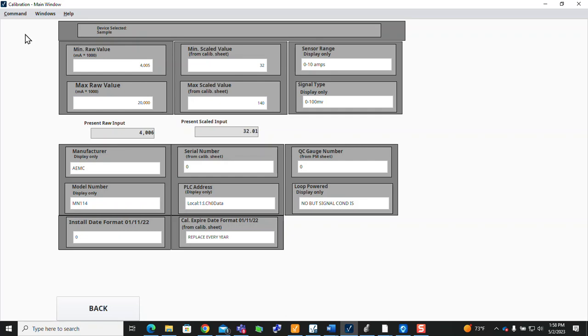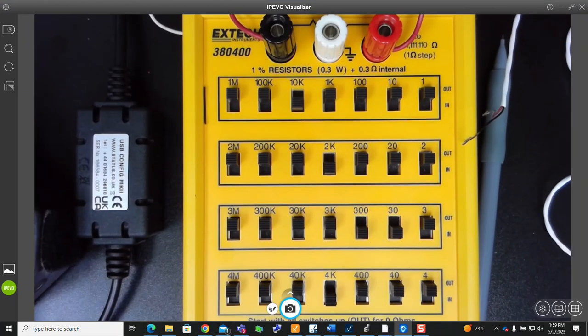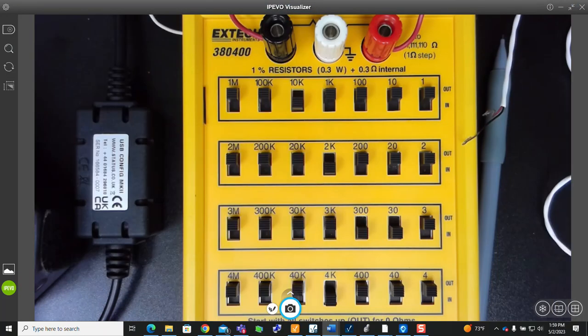Now we're going to go reconfigure our box for the high side. Make sure that the min and max here match, because if you're doing a new calibration, the values that we have been using are not correct. I'm not saying the calibration isn't off, but they played around with the numbers to get it close. It's not precise for our ISO calibrations. So we've picked 32 degrees Fahrenheit and 140 degrees Fahrenheit, so our resistance values come up with even numbers. Get your decade box. Now we're going to reconfigure for the high side. And if we look on our sheet, we'll see the high side of 140 degrees Fahrenheit equals 1244 ohms.